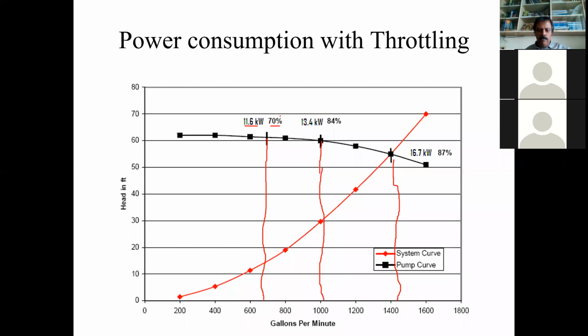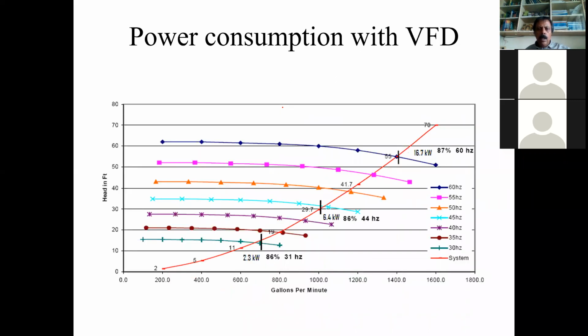We want the same variations to be met by a variable frequency drive. Initially the pump is operating at full speed, so at full speed there is no change, the same 16.7 kilowatt. And when you go to 1000 gallons per minute, we reduce the speed to such an extent that we get 1000 flow rate. At this point, you see the power is only 6.4 kilowatt.